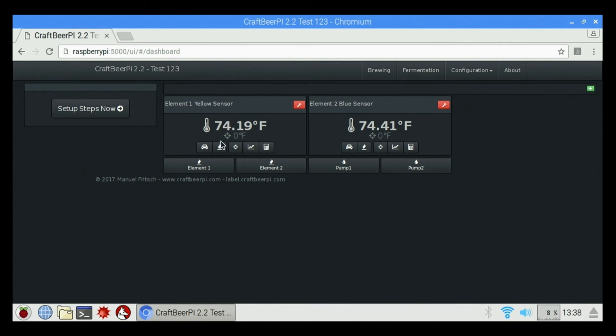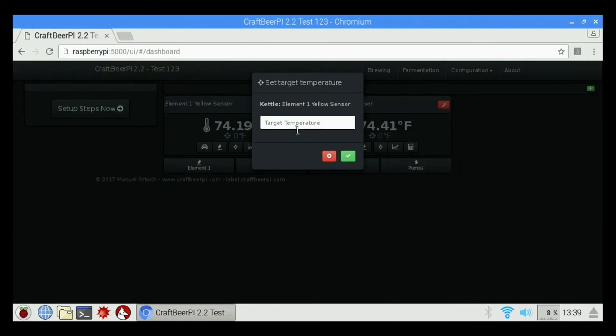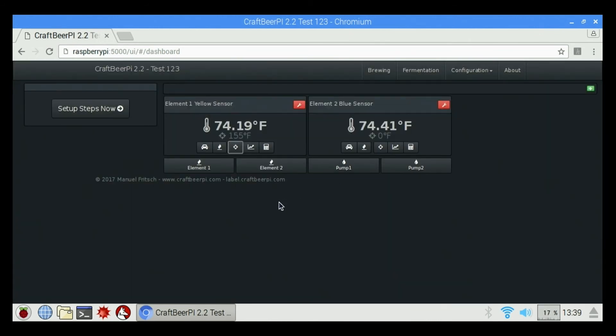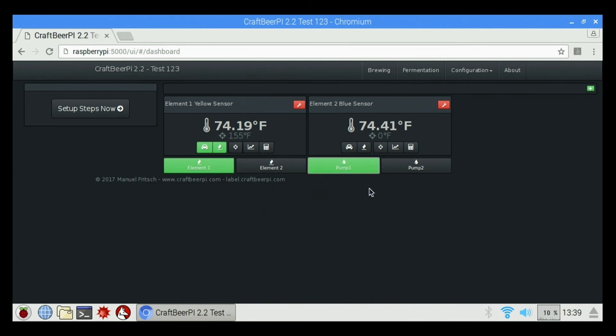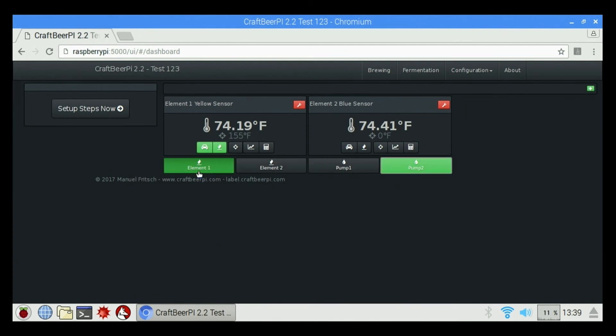So, to say I want to hit a certain target temperature with this, we have an auto button here and we have a manual. This is going to tell us when it's on. And we have a target for a target temperature. So we're going to click on our target. We're going to set our temperature to 155, or whatever you want to set it to. You have to have a target temperature set for it to turn on. So click on here first, set your temperature. Then if you click on auto, it's going to show you that element one is on and it's also on the controller. And it's going to heat the water until it's 155 degrees. We can turn on our pumps and click on auto again and it's going to shut it back off again.